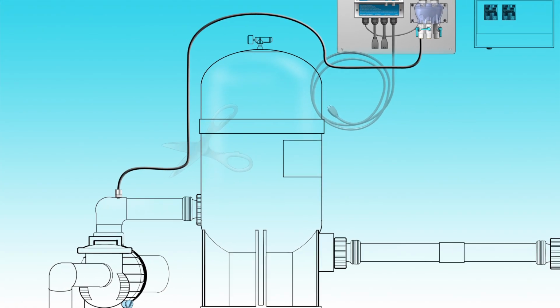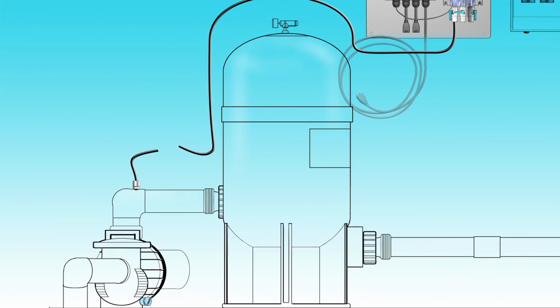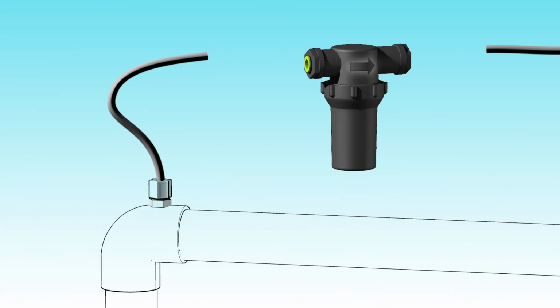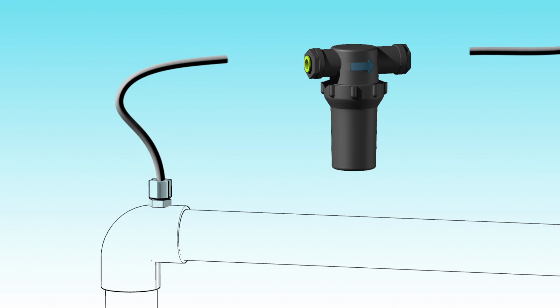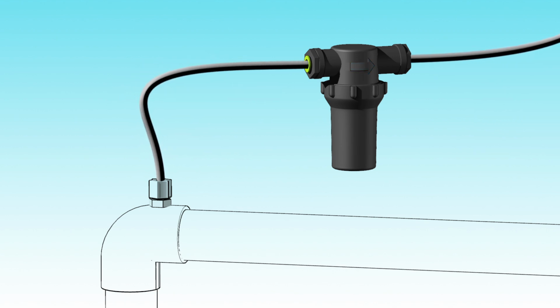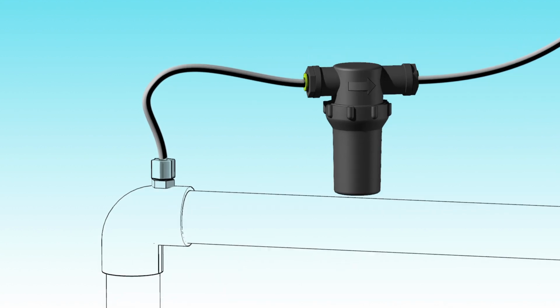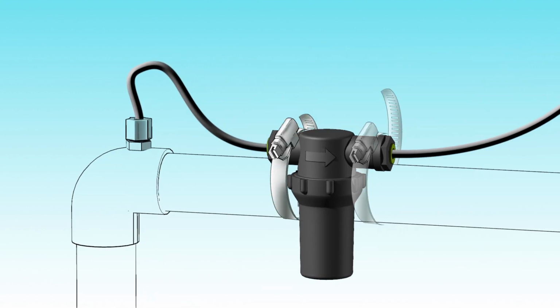To install the inline strainer, cut the tubing. Orient the strainer so that the arrows on the top are pointing in the direction of the flow of water, away from the pipe and toward the flow cell. Insert the ends of the tubing into the push-to-connect fittings on either end of the strainer. Using hose clamps, secure the strainer to a pipe.